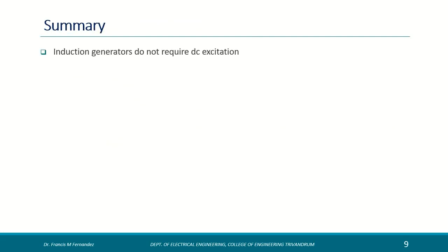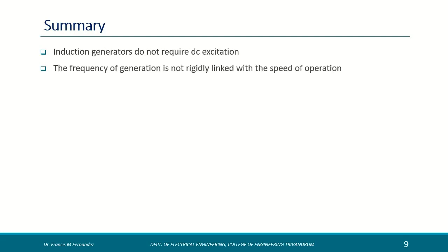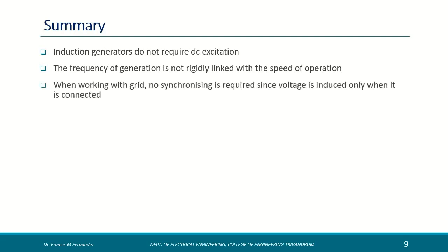In summary, we shall see the important features of induction generators. Induction generators do not require DC excitation. The frequency of operation of induction generators is not rigidly linked with speed of operation when it is working with the grid. No synchronization is required since the voltage is induced only when it is connected to the grid.